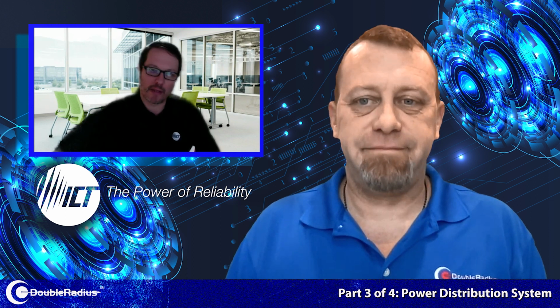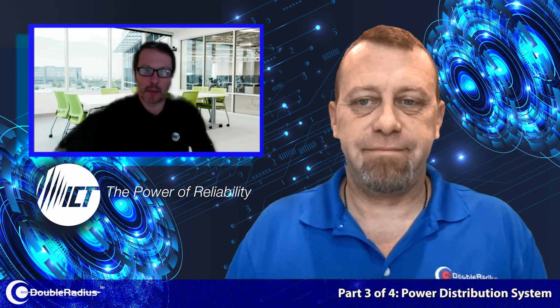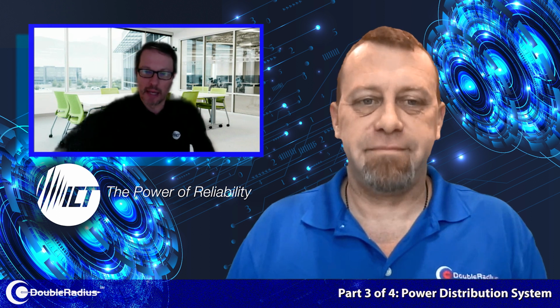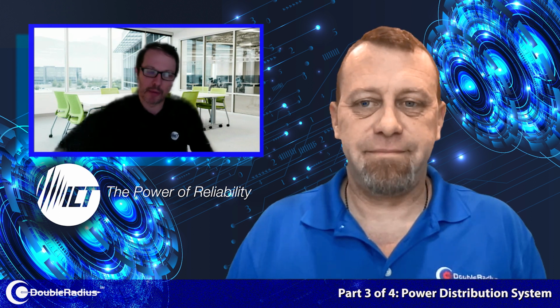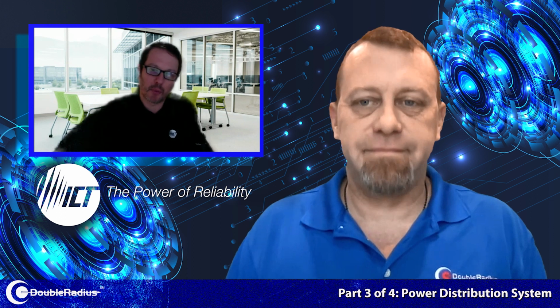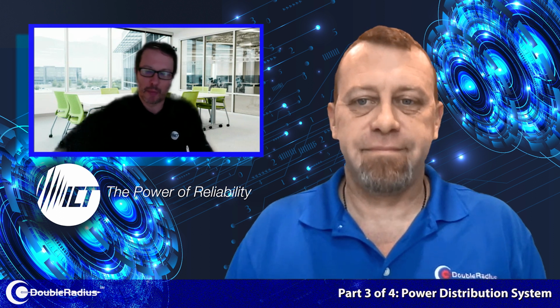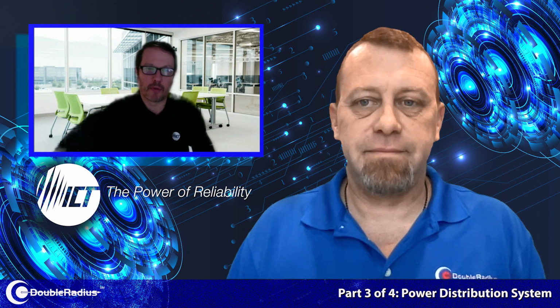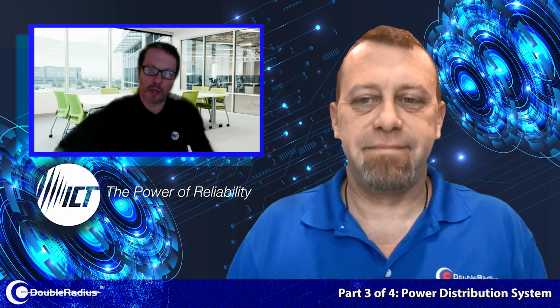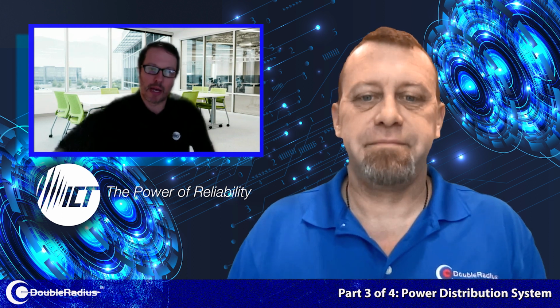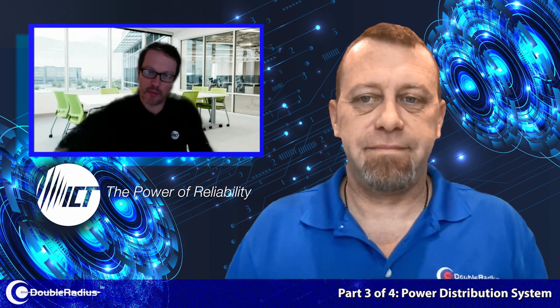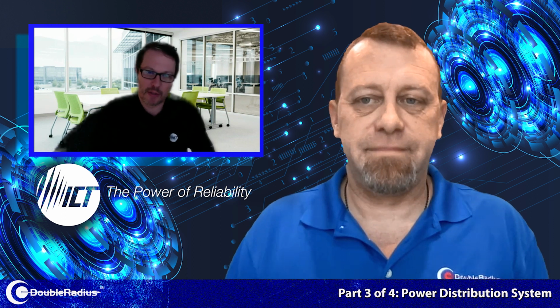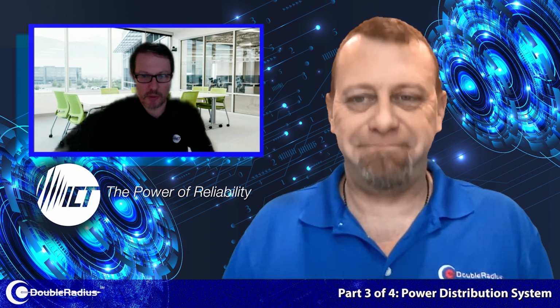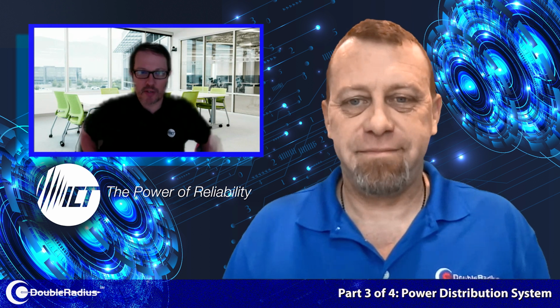What that does is it feeds the voltage coming from the DC power plant, the power supply or the power system, into the DC distribution panel. And then there are multiple connection points on the distribution panel. We have various different panels with different numbers of outputs, and those are where you connect your load devices. So now you have individual connection points for each of your load devices. That's the concept behind DC distribution. It's fairly common in the telecommunications space.